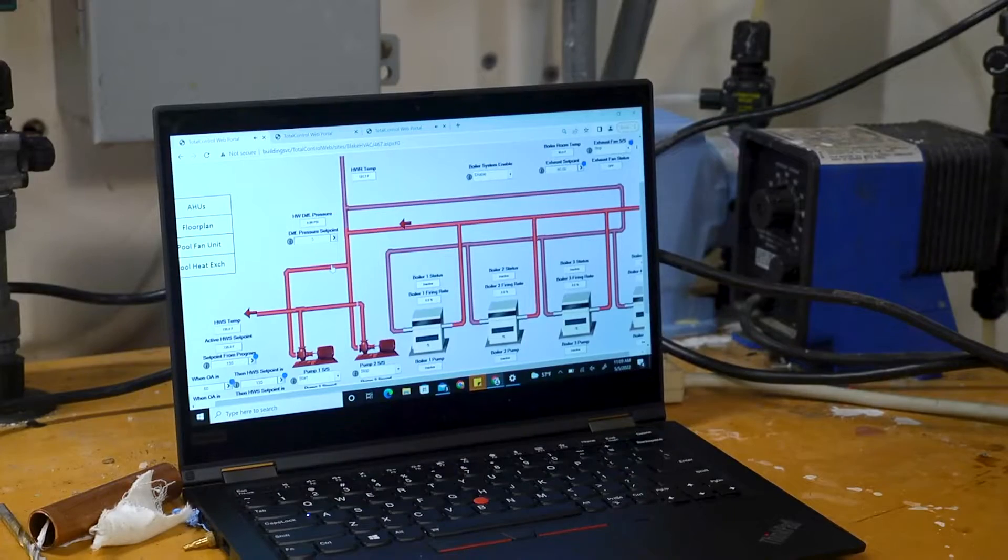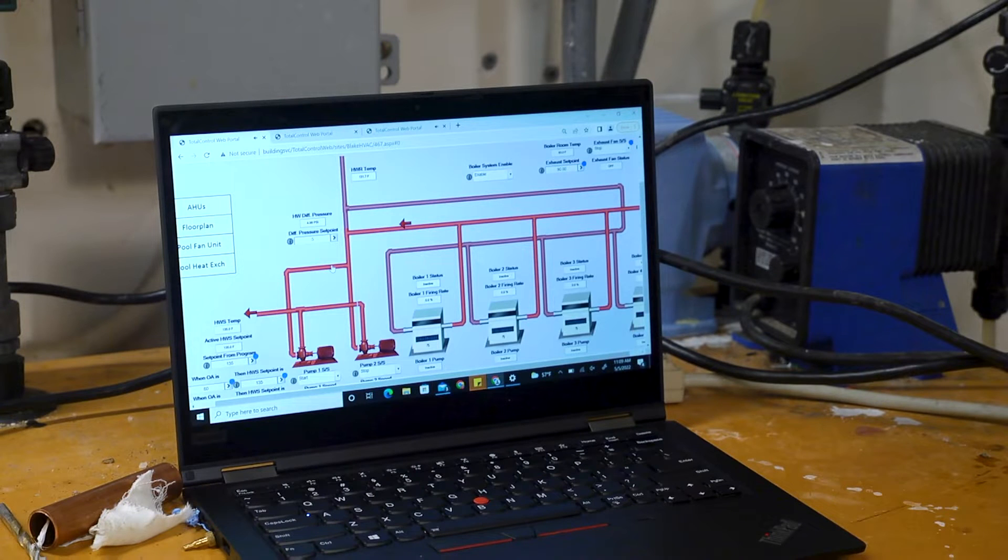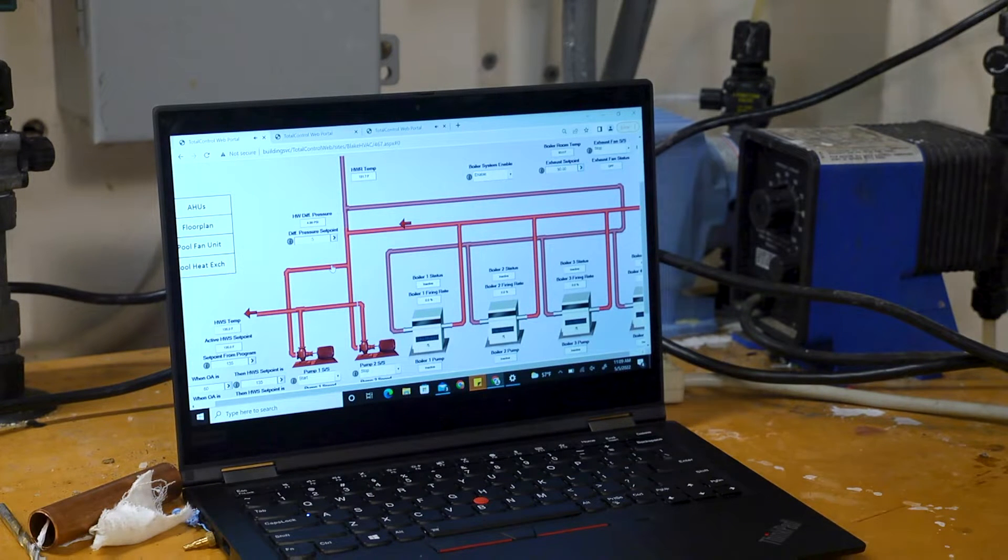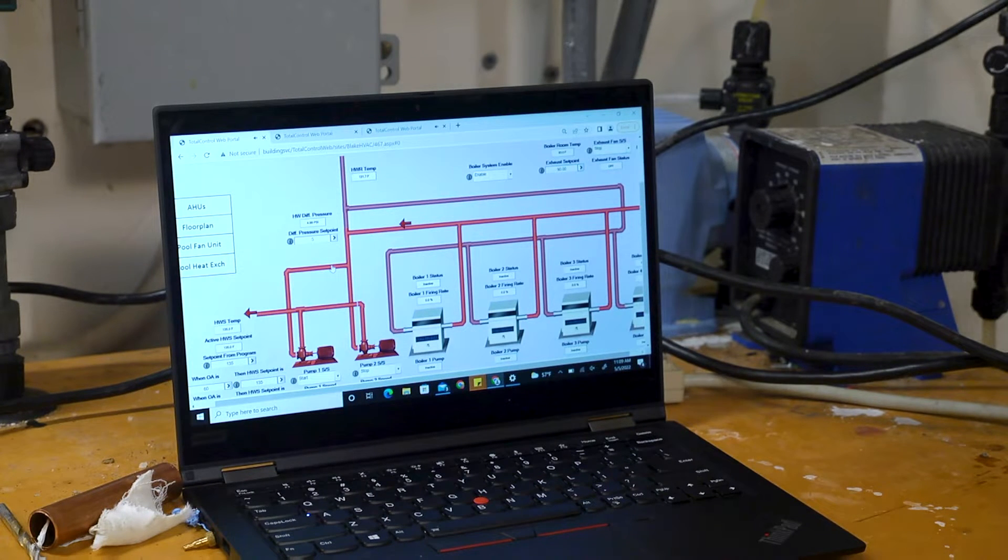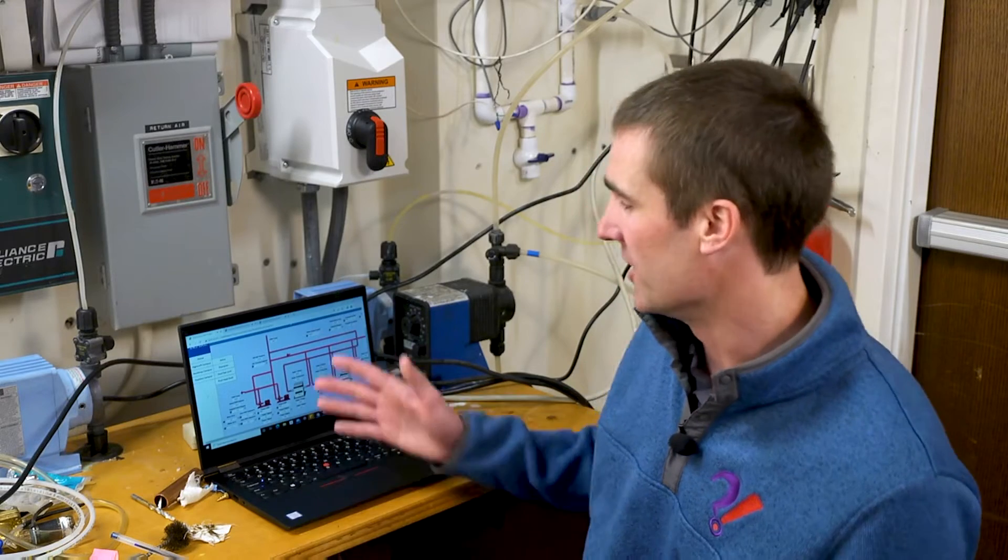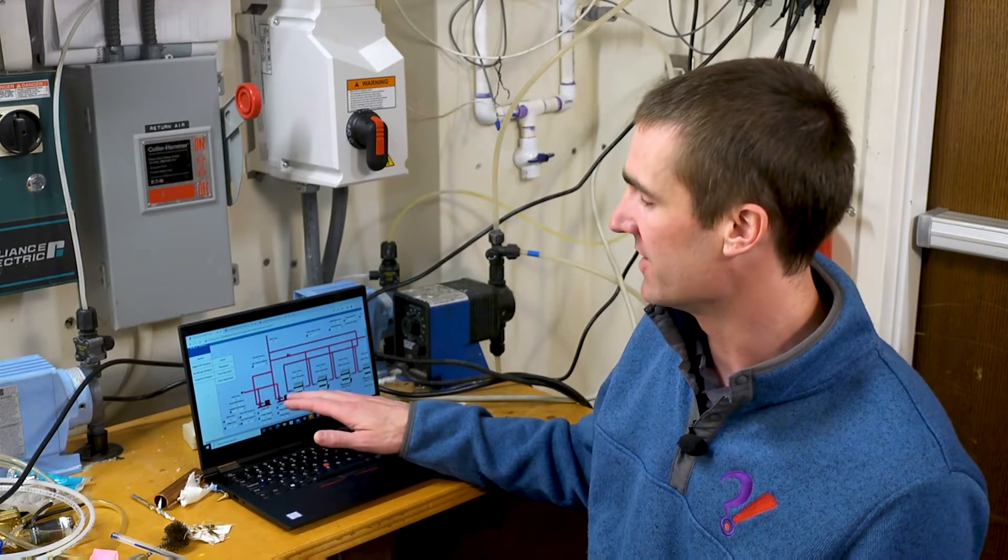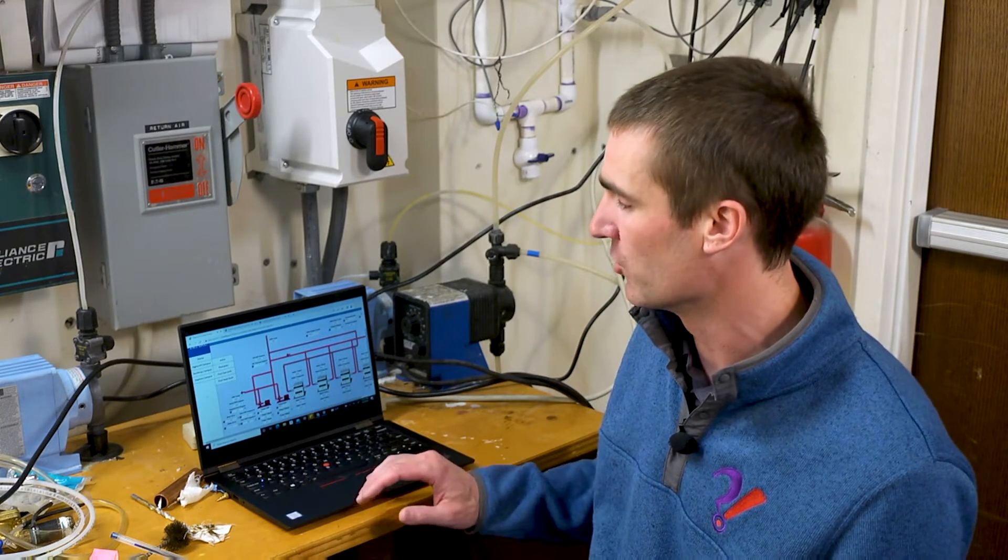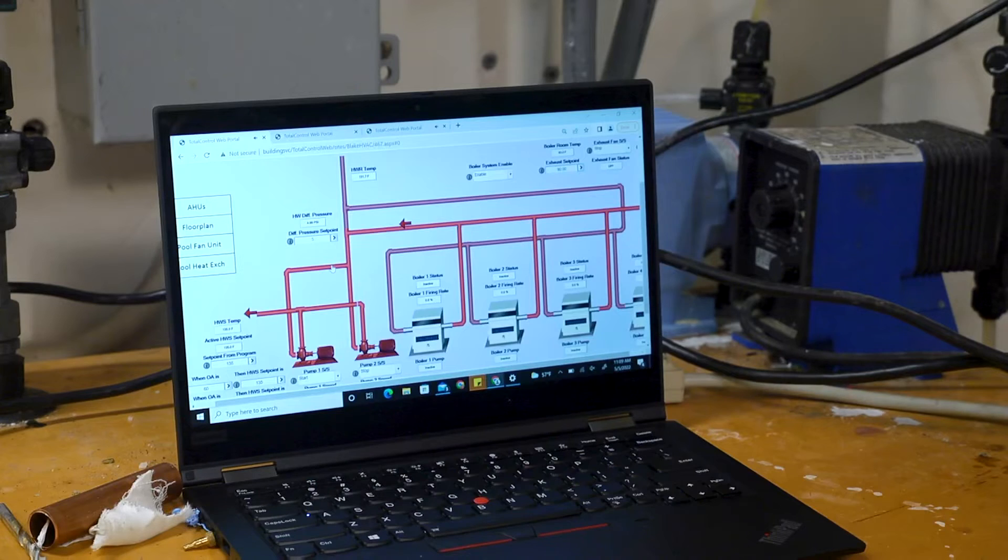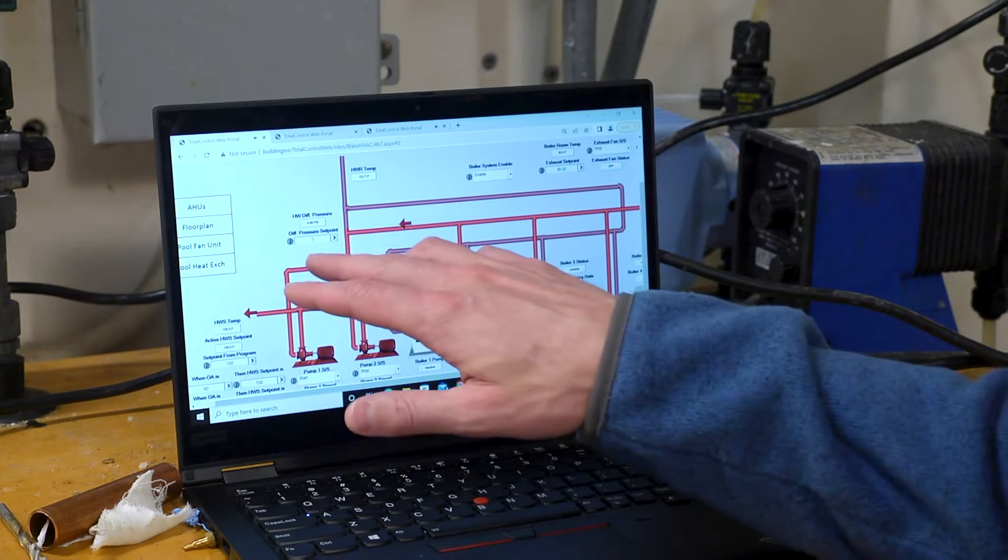Some building automation systems have the ability to flag when a set point has deviated from what it should be. In this particular case, we have secondary hot water pumps on this heating hot water system which control to a differential pressure set point of 5 psi differential.